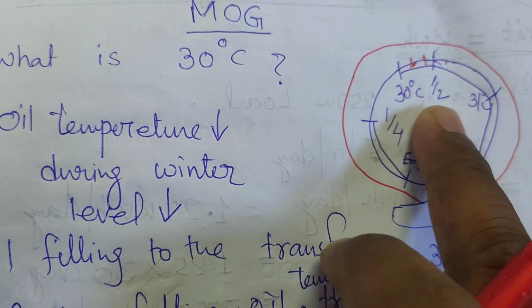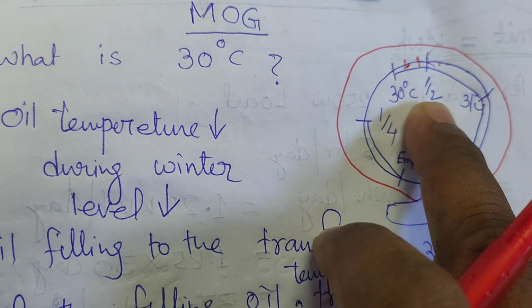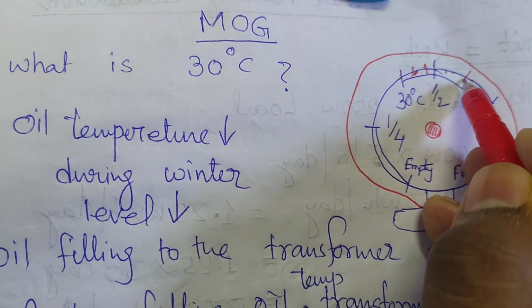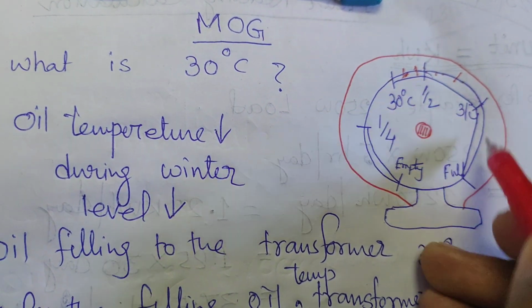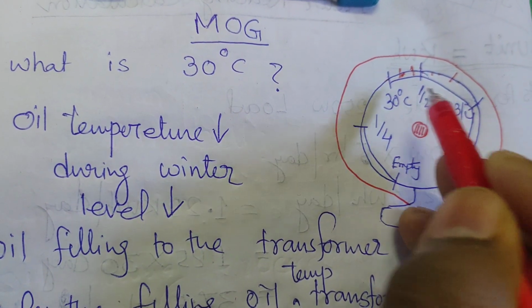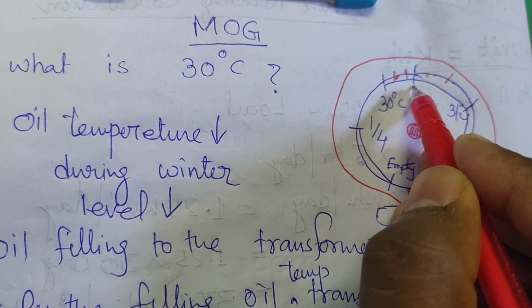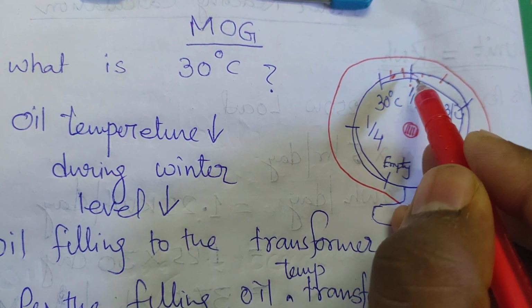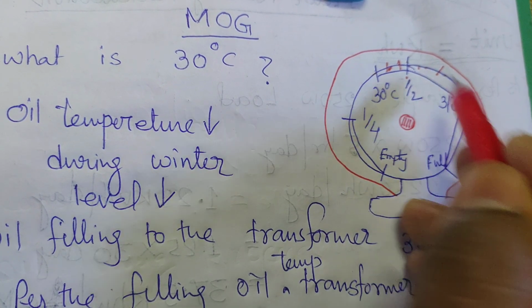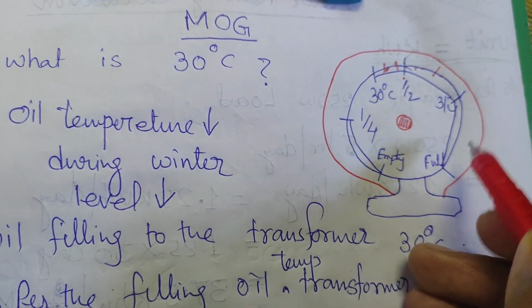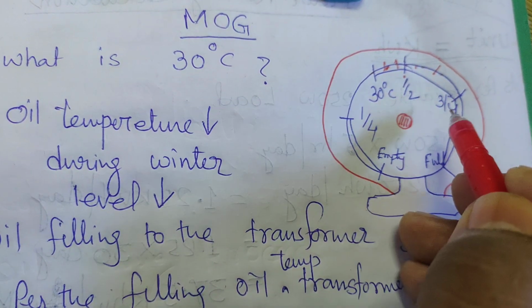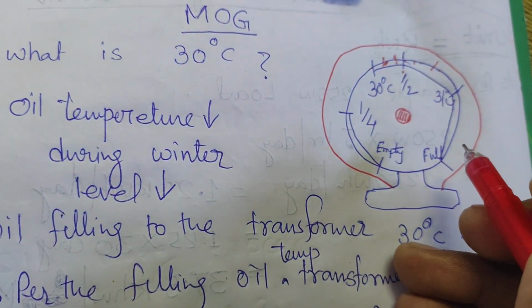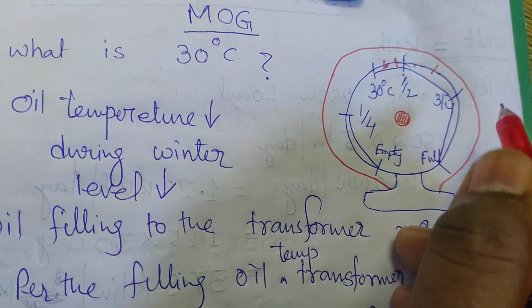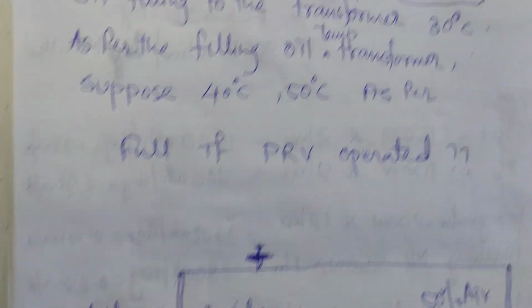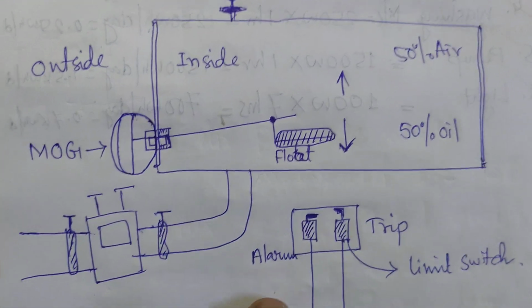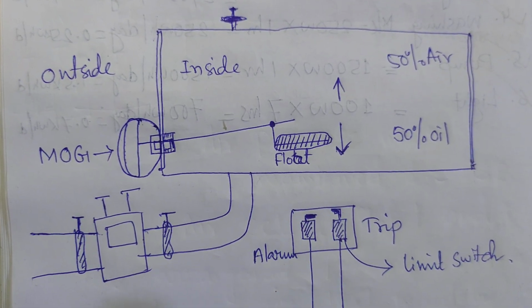If you want to fill half, you can do it, and up to this position you can do it. You have to provide this space for the expansion, so you can fill up to half of the conservator. This is technically good. If you are filling 3/4 of the oil, it is not technically good. The expansion space will be low. If the load increases, the oil will expand exponentially, and that will affect the transformer PRV operations. So I have drawn a picture for your understanding, friends.